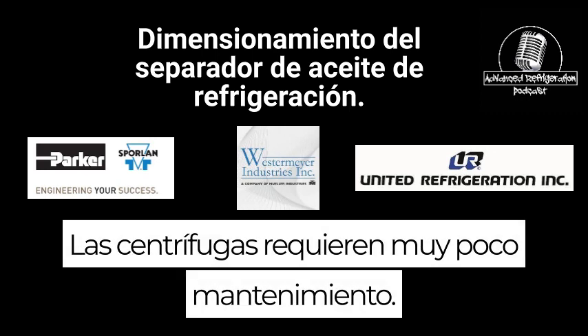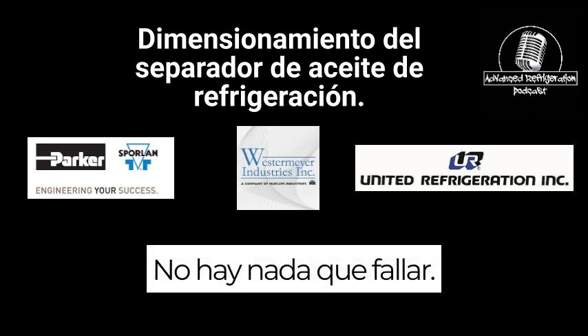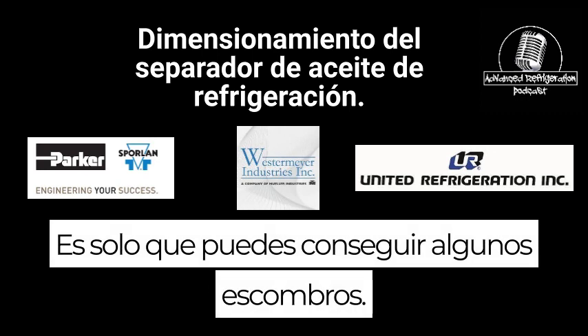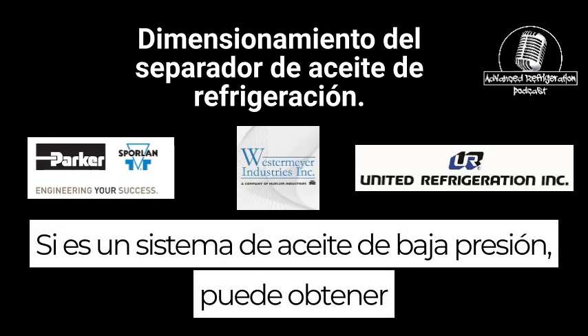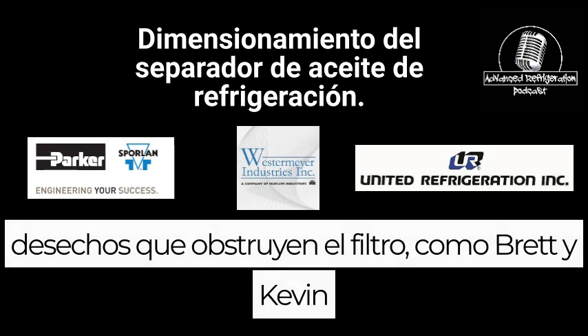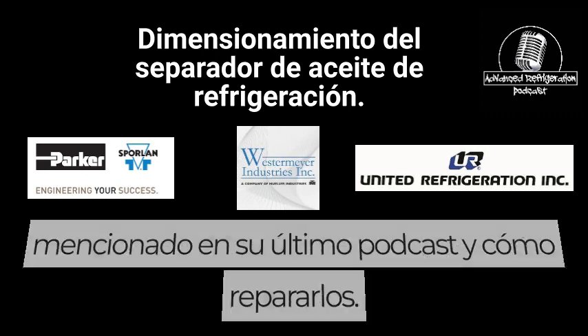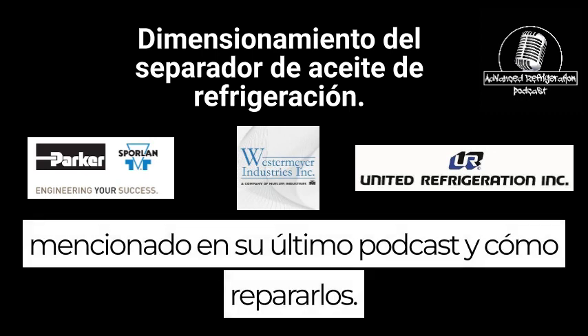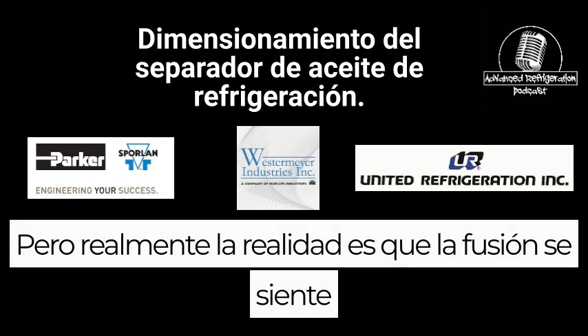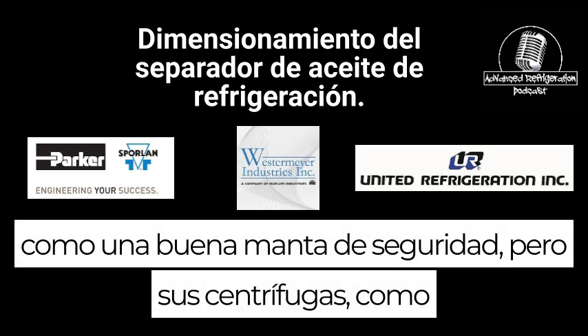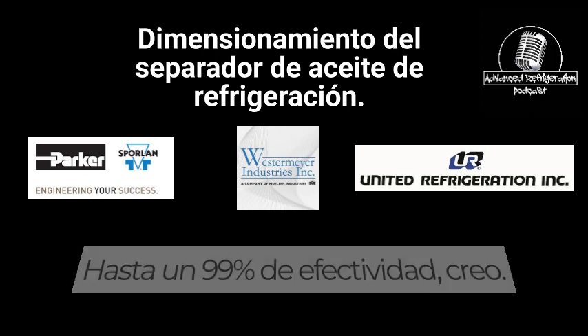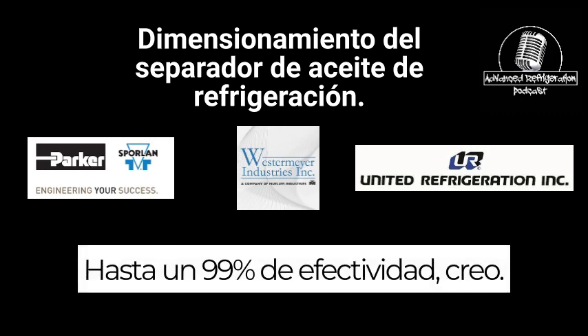Centrifugals are pretty low maintenance. There's nothing to fail. You can get some debris if it's a low pressure oil system, debris that clogs up the filter, like Brett and Kevin mentioned in their last podcast, and how to service those. But the reality is the coalescing does feel like a good safety blanket, but centrifugals, as long as they're sized properly, are good up to 99% effective.